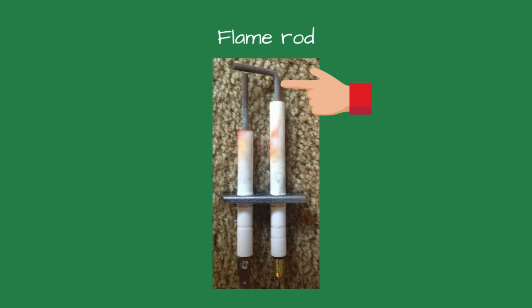Number 4, inspect and clean the flame rod or sensor. A dirty or coated flame rod drops signal strength. Remove the pilot assembly if needed. Clean the rod with steel wool or emery cloth. Avoid using sandpaper. It leaves a conductive residue.